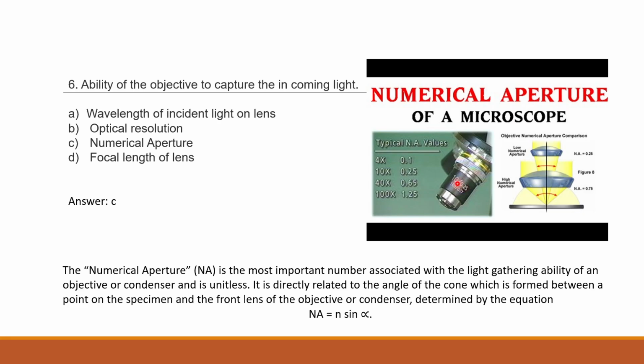Usually in recent microscopes they write it as 10x. If they have written it as 10x, you can understand that it is magnification, because x we use for magnification. And then beside that, if there is some 0 point value or 1 point value, that is the numerical aperture of that. And then what else is written, some 160 by 0.17. So these are all different things that they write.